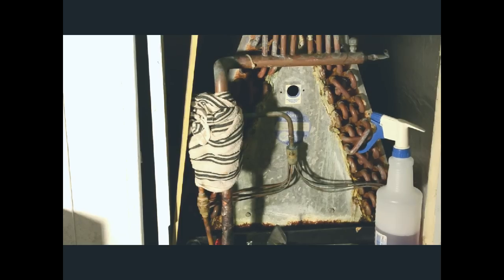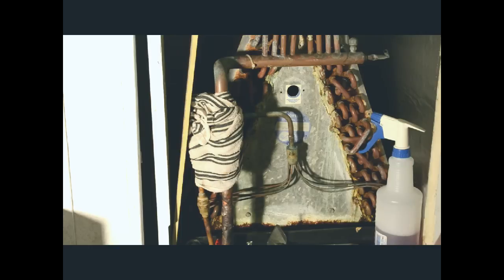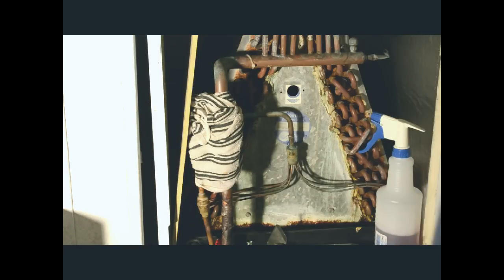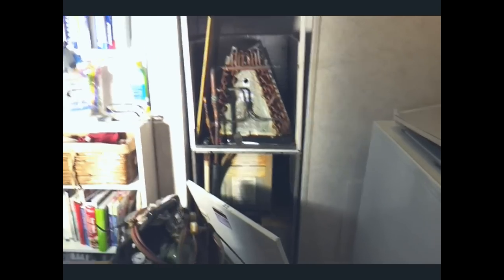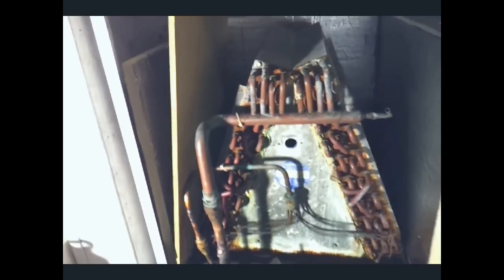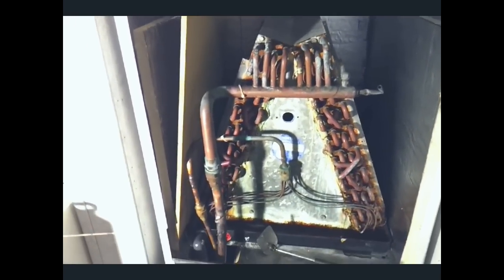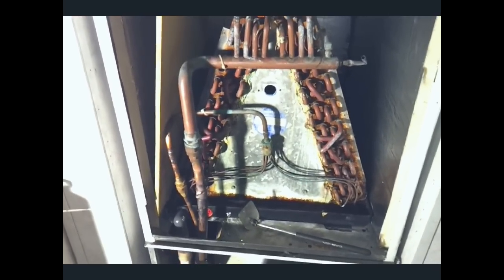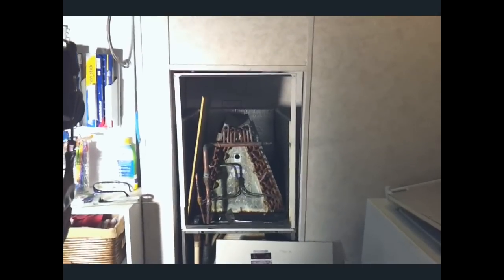Most of the welding done, put some soap bubbles on it and I have a leak not on the back but on the front right on the corner where I didn't quite catch it. So get that sealed up and then hopefully round two will be the miracle worker. All of our leaks are settled out, our welds are finished looking good. Sam has been surfing a little bit while I've been finishing this up. Now I have the equipment outside going. It's pulling a nice hard long vacuum. I'm going to get with Sam and we're going to start working on putting the rest of the filter base set up for the top.